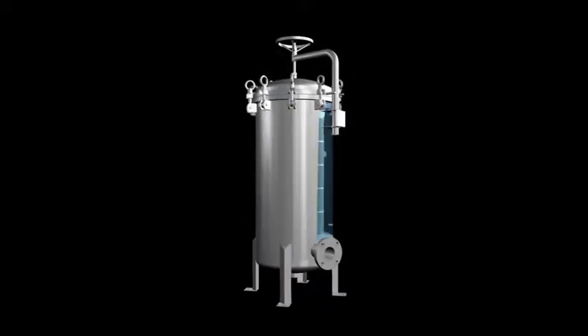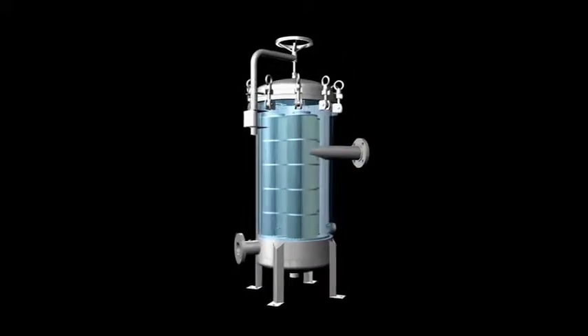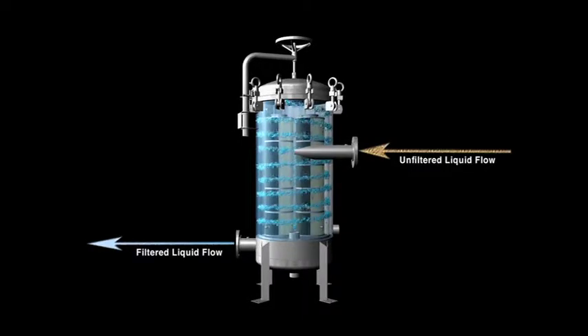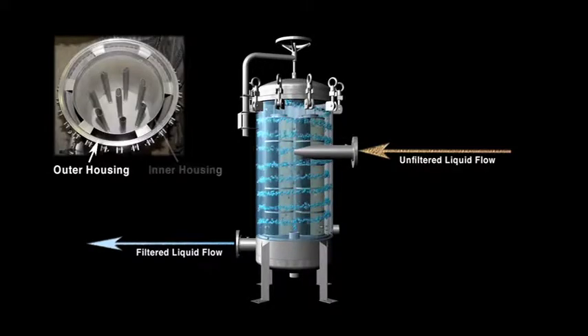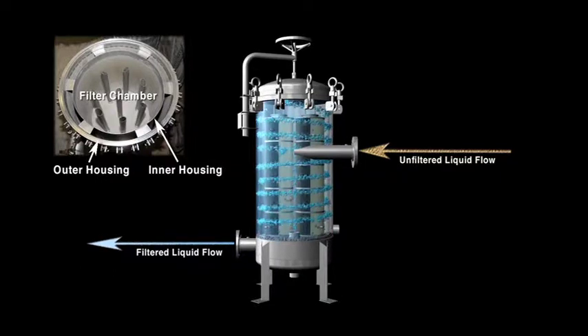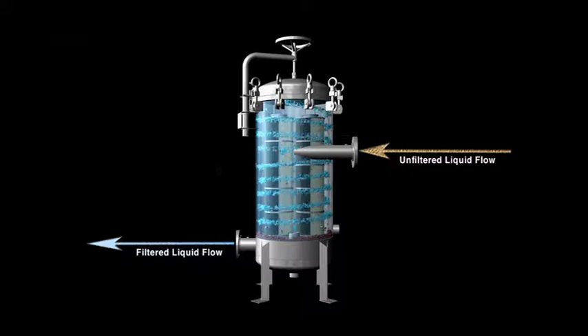Here is how the Hurricane filter works. The liquid flows into the housing through a tangential entry and is channeled between the outer housing and the inner housing wall. The inner wall rises from the base to just below the top of the housing, so that liquid must flow around and then over the inner wall before entering the cartridge filtration area. This outer flow creates a cyclonic effect.